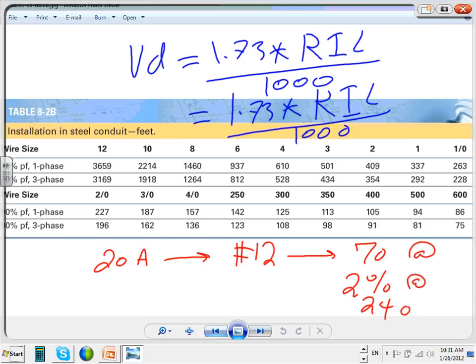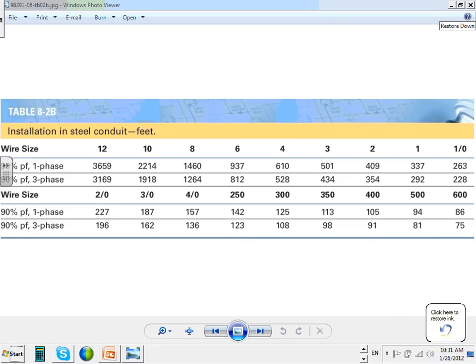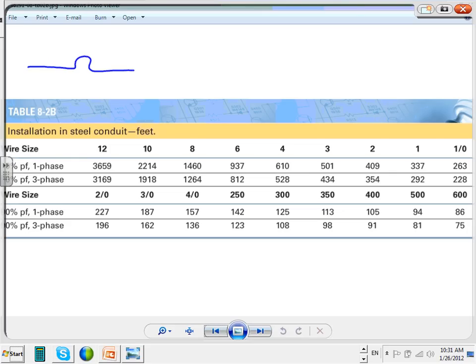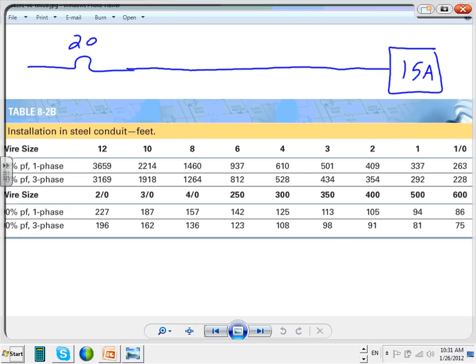I'm going to go to one very simple example for you guys on the same page, 1-23. I think it's a very good example. Take a 20 amp circuit, and out of the 20 amp circuit I'm going to pull a load, and I'm going to make my load 15 amps. The voltage is 120 volt, single phase, right? It's a branch circuit, and I need to maintain an engineered voltage drop of 2%. I can go to 3%, but bad news. In a branch circuit, you always maintain it to 2%.